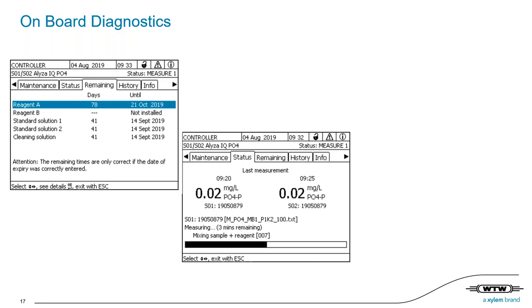Okay, and is the daily calibration or cleaning started by the user or automatically conducted by the machine, by the Alyza itself? Great question, thanks. It's automatic cleaning and calibration. As I mentioned, for the P700, we already introduced an automatic cleaning and an automatic 1-point calibration. But for the new Alyza, we also have an automatic 2-point calibration. So you can always choose what you need.